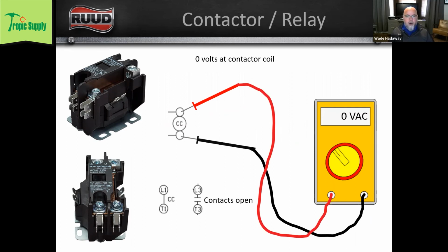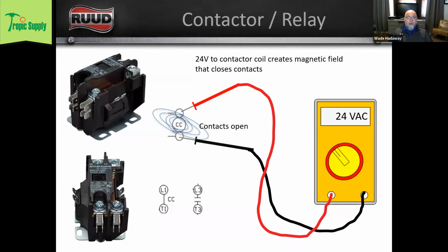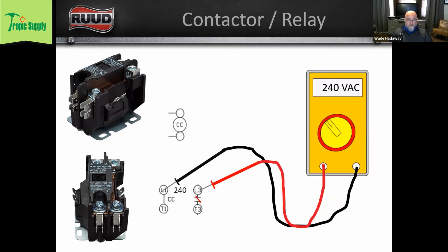So on the top, we've got our low voltage. That's our contactor coil. On the bottom, we have got our set of contacts. And when we apply 24 volts to our contactor coil, that creates the magnetic field that closes L3 to T3. And so here we were talking about voltage and voltage drop. So we have no voltage issues.